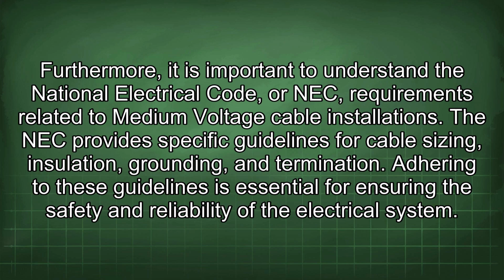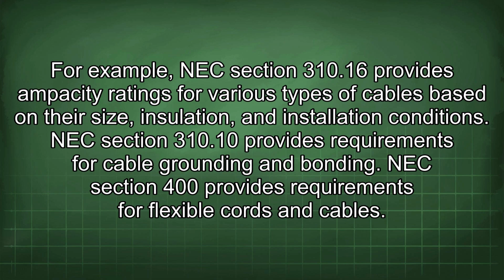Furthermore, it is important to understand the National Electrical Code, or NEC, requirements related to medium voltage cable installations. The NEC provides specific guidelines for cable sizing, insulation, grounding, and termination. Adhering to these guidelines is essential for ensuring the safety and reliability of the electrical system. For example, NEC Section 310.16 provides ampacity ratings for various types of cables based on their size, insulation, and installation conditions. NEC Section 310.10 provides requirements for cable grounding and bonding. NEC Section 400 provides requirements for flexible cords and cables.